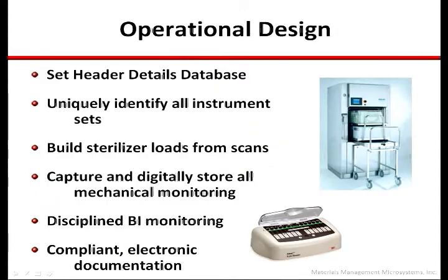The operational design of DSA is straightforward. The Set Header Details database allows for all deliverable items to be uniquely identified with barcode labels that include set name, description, and other key information. All mechanical and machine control monitoring from washing and sterilization cycles can be captured and stored as part of compliant documentation policies.